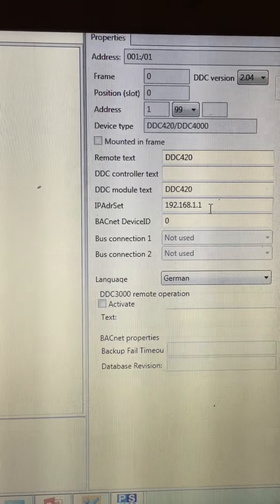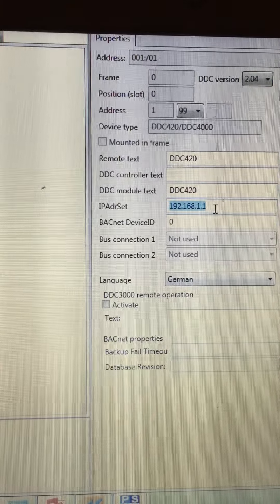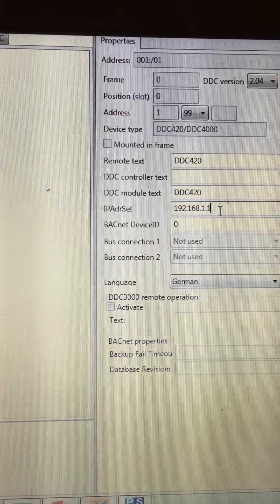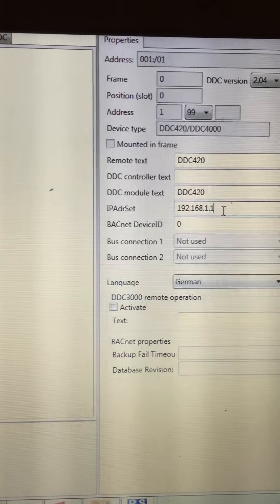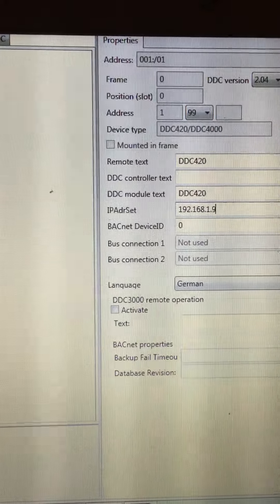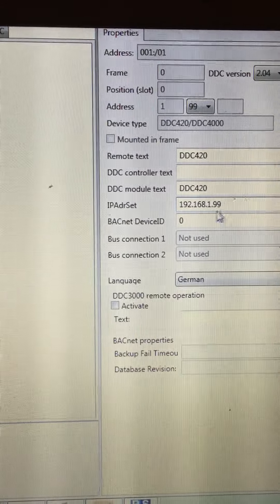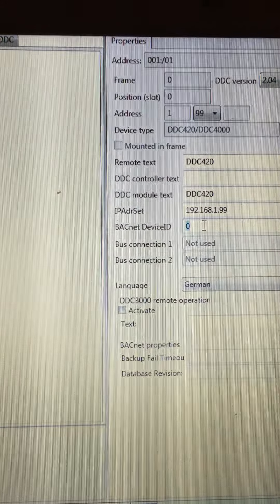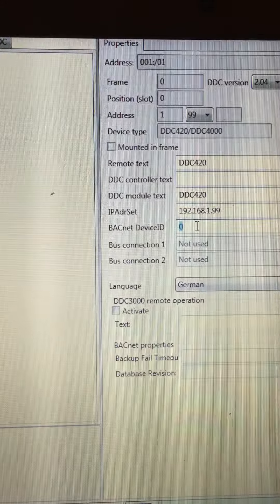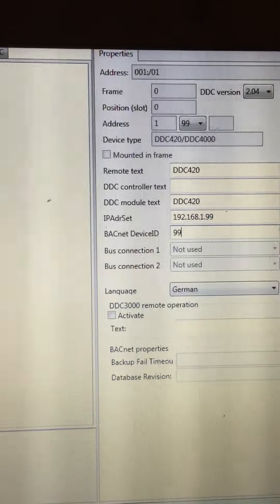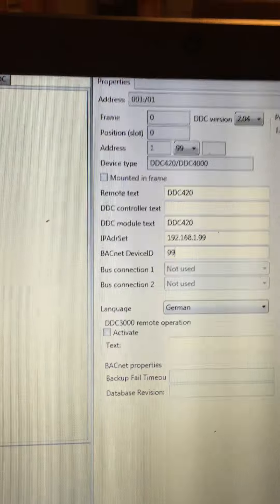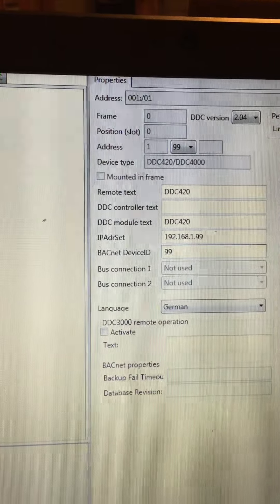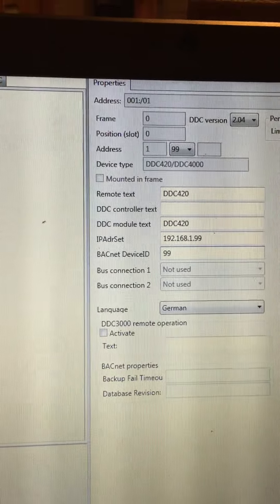The second setting is I need to give it the address of 192.168.1.99 and I now need to give it the BACnet device ID of 99. So that's the three addresses on the DDC controller itself.